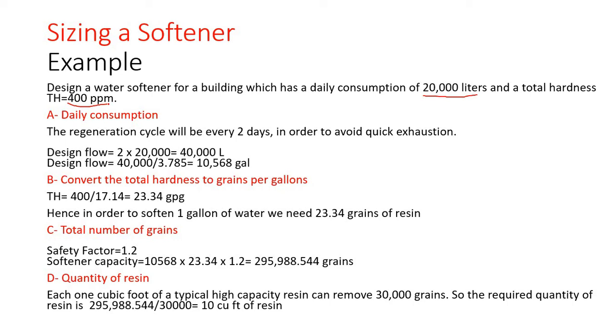First of all, we need to adjust the daily consumption. Because the softener has resin and the capacity of the resin can be quickly exhausted. We need to rinse this resin with a salt solution, that's why we have to choose a regeneration cycle. Here we have chosen a cycle every two days, so every two days we will rinse our resin with a salt solution.